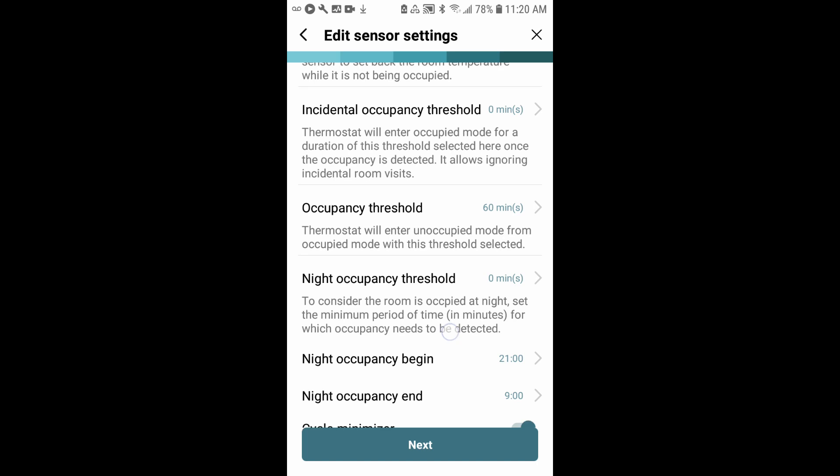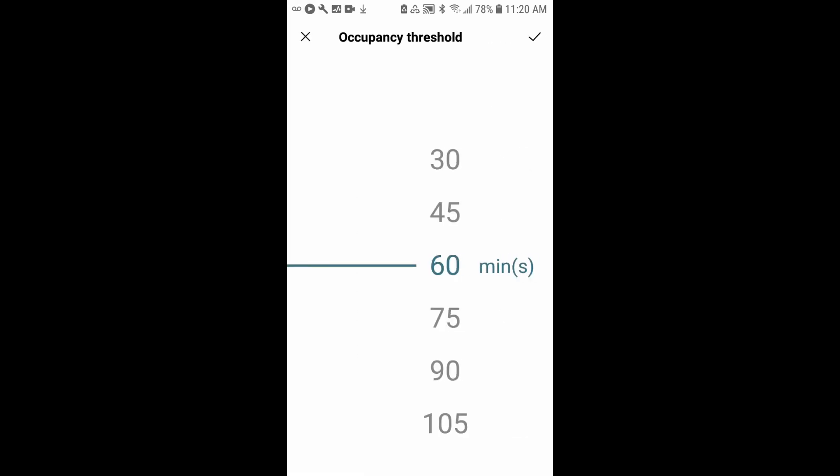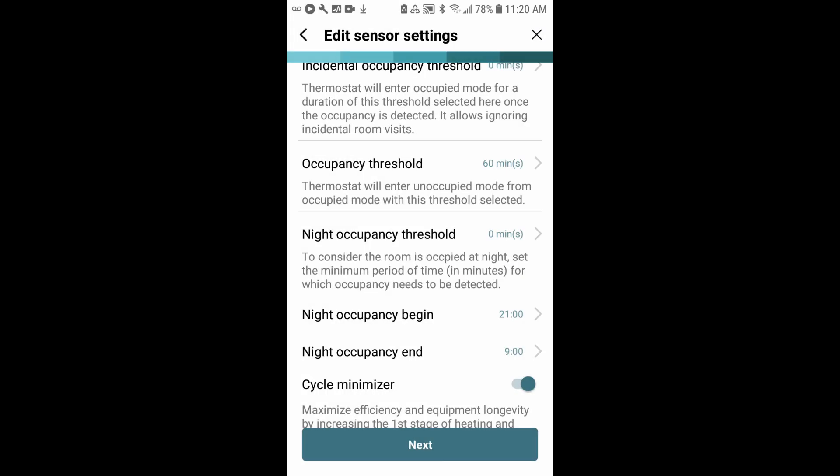The occupancy threshold is set at 60 minutes. This is the time that when the system detects occupancy, it will run for 60 minutes before it checks for occupancy again. It will consider the room occupied for that 60 minutes. Again, you can adjust that time frame anywhere from you want it to check every 30 minutes all the way up to 105 minutes. Leave that at 60.